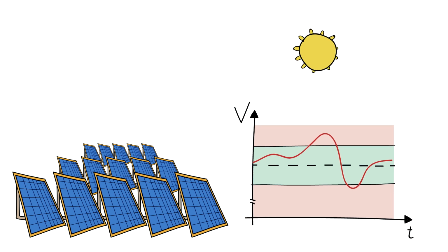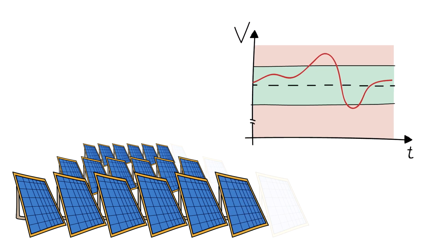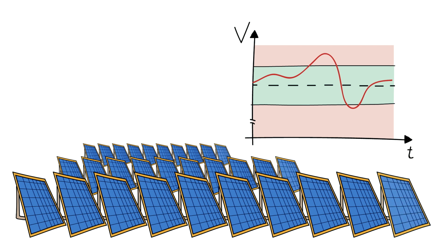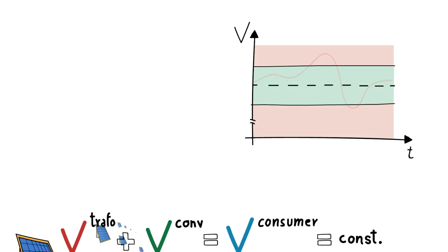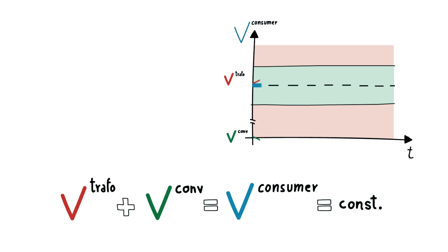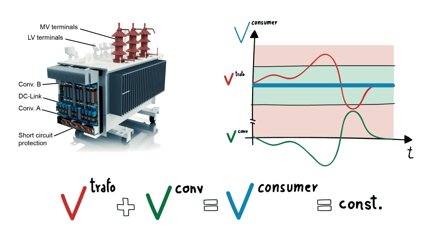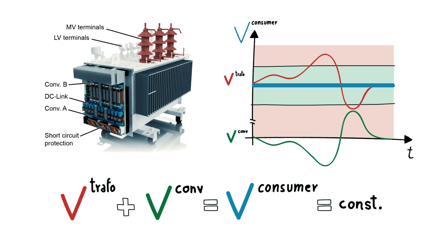If more and more renewables, such as photovoltaics or wind power plants, are installed, the grid voltage leaves the permissible range. A fast and dynamic grid voltage control is required. Advanced power electronic solutions are especially suitable to compensate such voltage fluctuations.